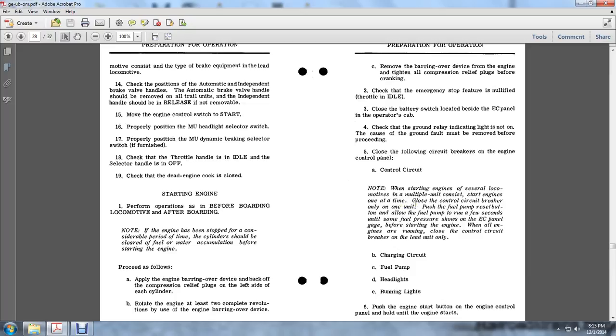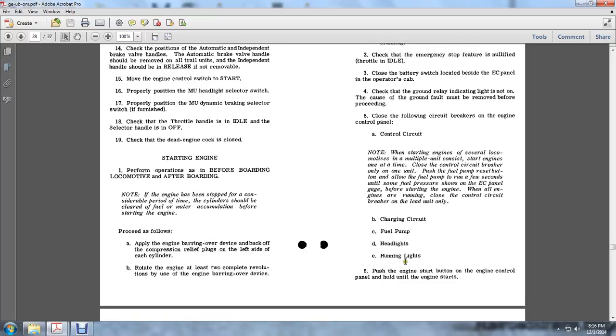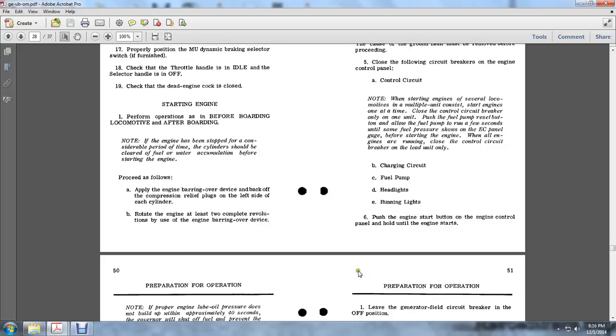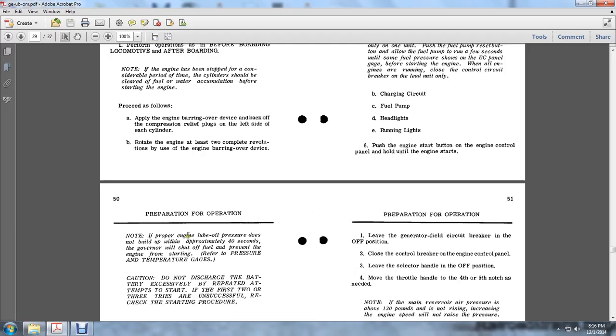Push the fuel pump reset button and allow the fuel pump to run a few seconds until some fuel pressure shows on the engine control panel. Before starting the engine, when all engines are running, close the control circuit breakers on the lead unit only: the charging circuit, the fuel pump, the headlights, and the running lights. Push the engine start button on the engine control panel and hold it for the engine to start. Note: if proper engine lube oil pressure does not build in approximately 40 seconds, the governor shuts off the fuel to prevent the engine from starting.